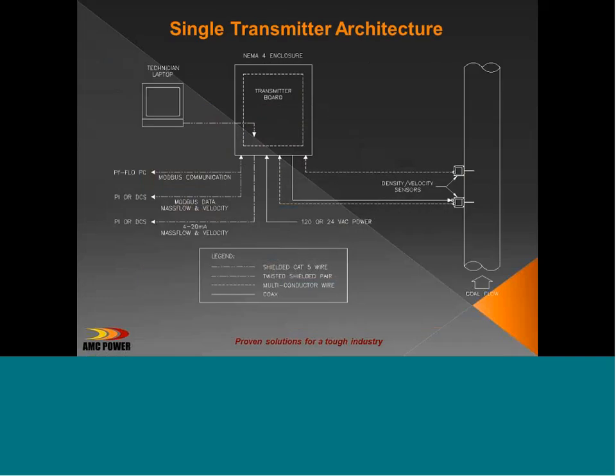The sensors are connected to a transmitter, which is located in the field, usually up on the burner deck somewhere. And that transmitter does all the work. So we're doing the conversion of the frequency curve shift to a mass flow, and the cross-correlation to a speed, all done in the field, and then we transmit those via 4 to 20 or digital back to the DCS and to our SCADA computer. Again, the SCADA being what is showing curves like this.